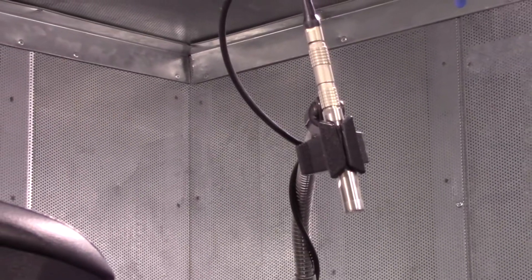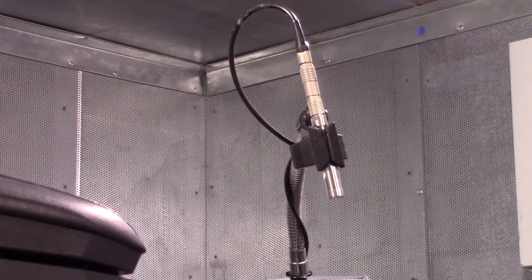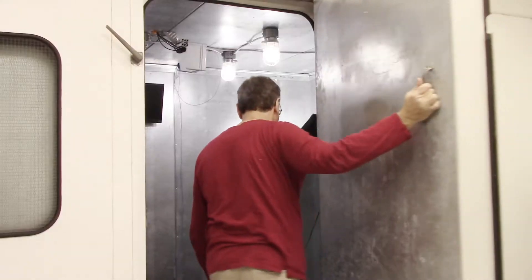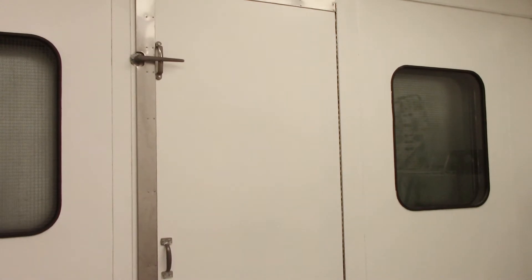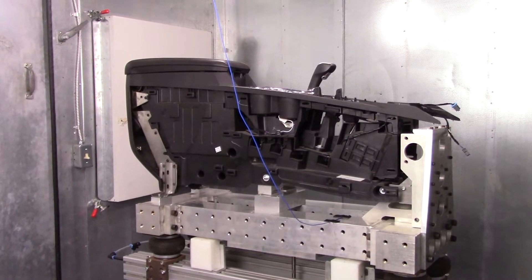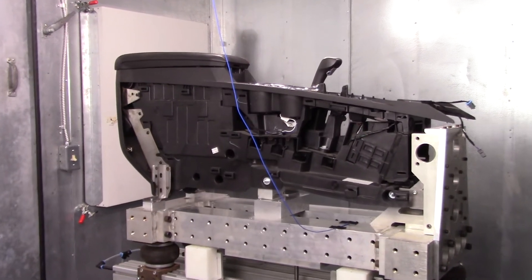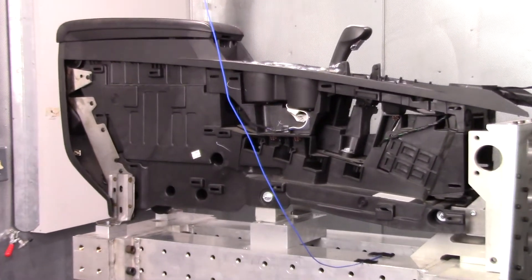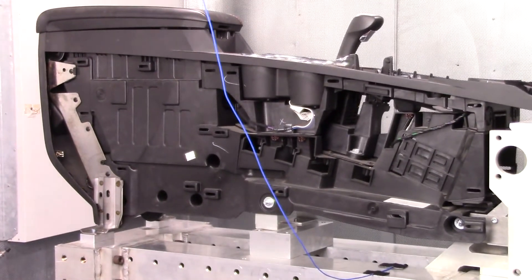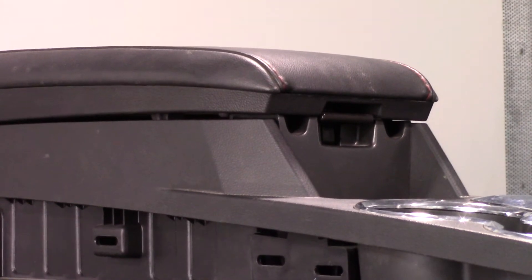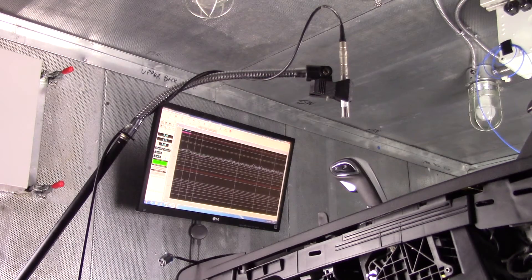While we can assist with the initial troubleshooting, generally the design engineer will need to be on site inside of the quiet room environment for this to proceed effectively. Troubleshooting can be a time consuming process. The engineer will require extended quiet time inside of the quiet room, up close to the DUT while it is vibrated at test level.